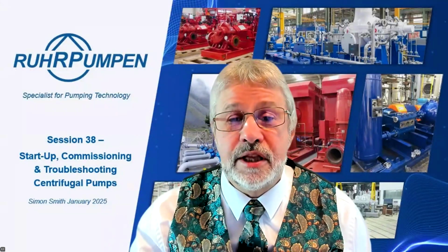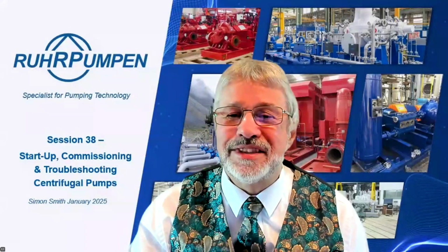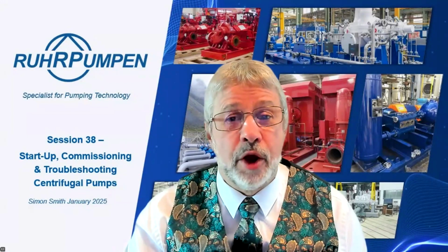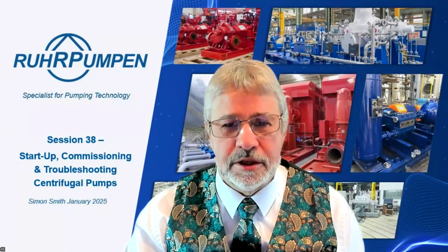Does Ruhrpumpen have low flow, high head models like 100 gallons per minute and 1350 feet? Yes, we can do that with VS6s. We also have a pump called a combi tube, which is a pitot tube pump. I might be doing a presentation on those pumps in the coming months, and they are low flow, high head. 100 gallons a minute, 1350 could also be in the range for a Sundyne pump, an OH6 pump, integral geared high speed pump.